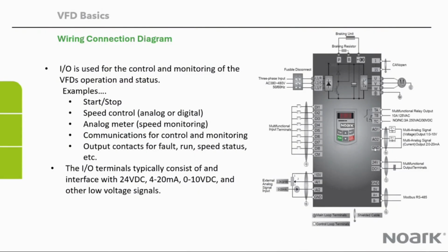We have an analog output here, which can be set up for different things. Voltage and current basically telling you, yes, we are running at that speed, and maybe what load is actually being drawn. It could be a 0 to 10, it could be a 0 to 20 milliamps. We also have a digital output that is like a relay, but it's just a digital output. It puts out a voltage and then indicates what's going on with whatever we programmed it for.